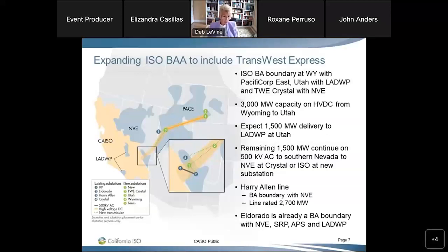All of the wind generation is expected to connect to the Wyoming substation, bringing about 3,000 megawatts down the DC line, which is why I colored it orange versus the dotted green, which is the 500 kV AC line. The 3,000 megawatts will run from the Wyoming substation to the Utah substation.